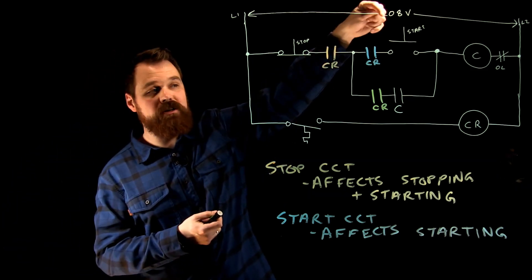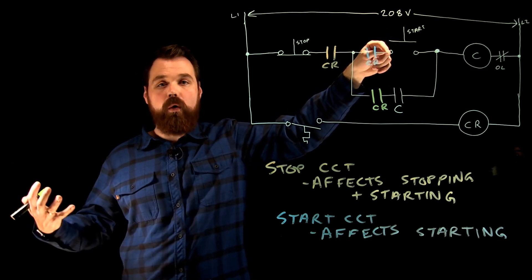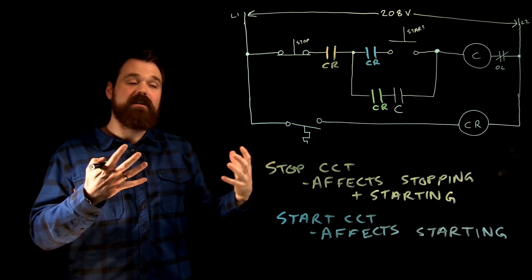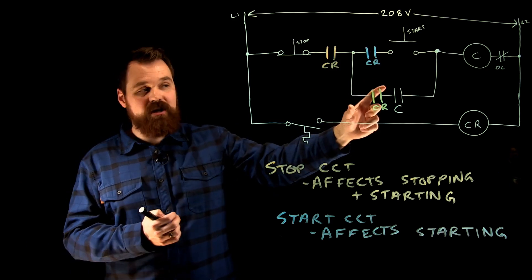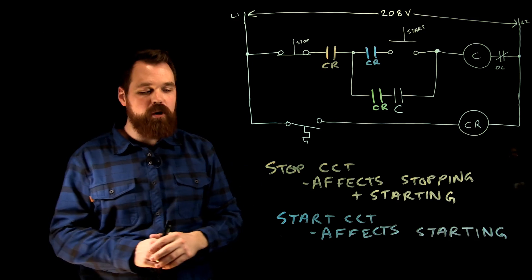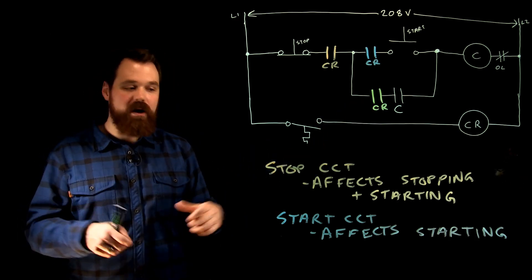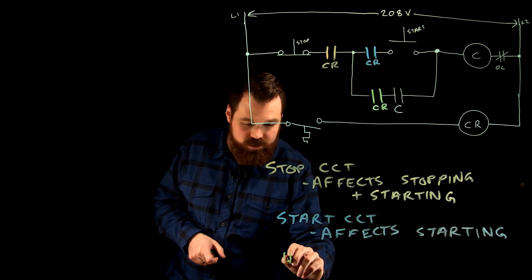However, we could still press the start button and start the motor. It just wouldn't hold. So we can actually call that a little bit of jogging in that if this set of contacts were to open, we can use the start button to jog or bump forward the motor. So all this set of contacts really affects is the holding or the running of the motor. So if we put it in the holding circuit, we just say it affects the running of the motor.